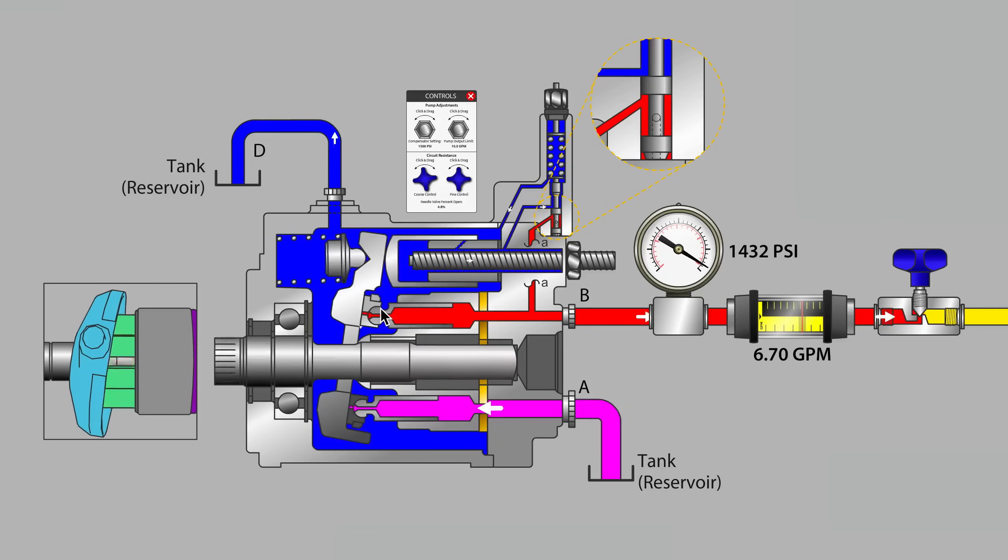There is also the piston ball which is crimped into place on the piston shoe. There's a minor amount of clearance there and all of the cylinder barrel on its porting face is rotating against a porting plate inside the piston pump as well. So there's a rotating piece and a stationary piece and that porting plate is a minor clearance as well.